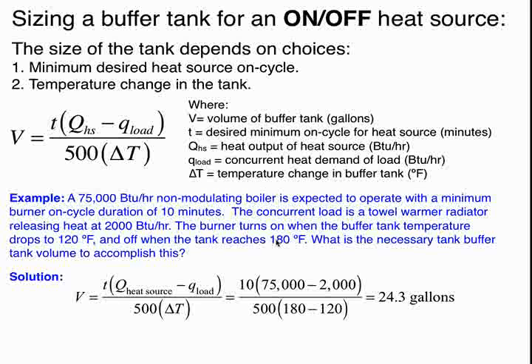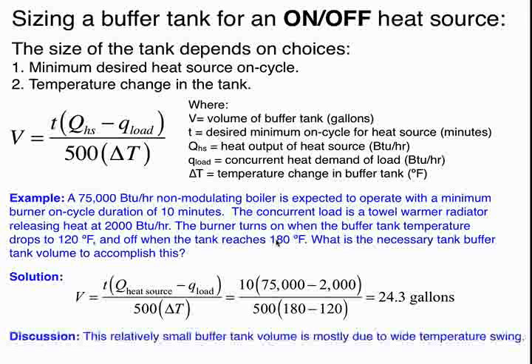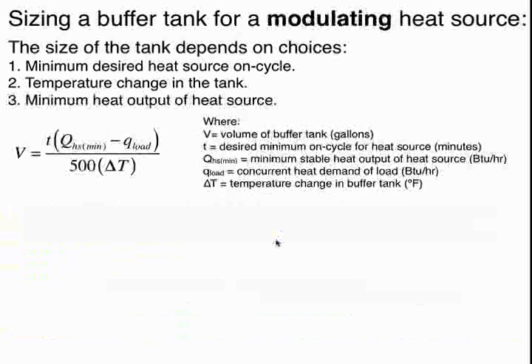So we put the numbers in the formula, calculate it out, and you can see it's not a large tank, just under a 25-gallon tank, and there are buffer tanks available. Caleffi has a thermocon at 25 gallons that could be appropriate for a situation like this. Again, widening the delta T is going to reduce the volume of the buffer tank, and anything that lengthens the on time of the boiler is going to increase the size of the buffer tank.